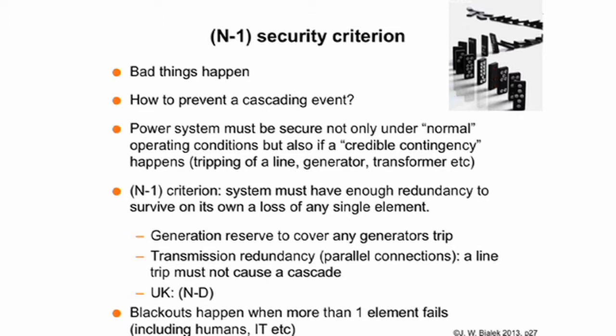So it means there must be enough redundancy built into the system to prevent failure if you lose a line, a transformer, a generator, whatever. That's referred to as the n-1 criteria, because one element can fail, and the system must have enough inbuilt redundancy to survive it on its own. That means there must be enough generation to cover any generator trip. It also has to have transmission redundancy, and that's why transmission networks are meshed.